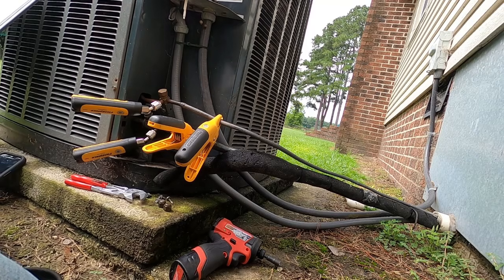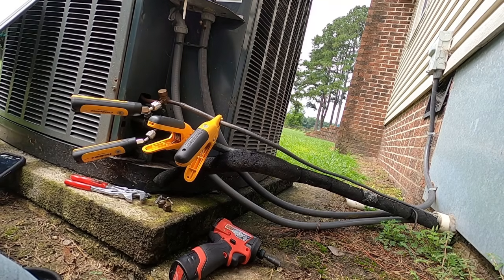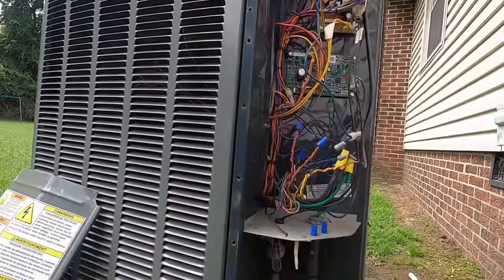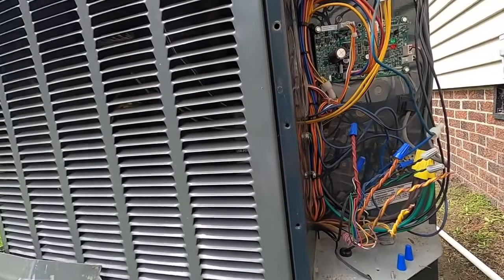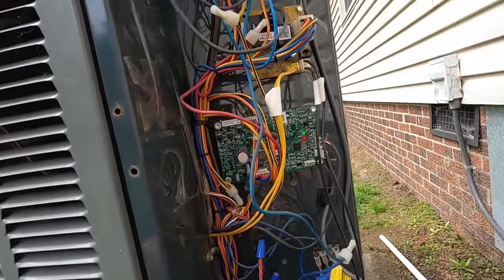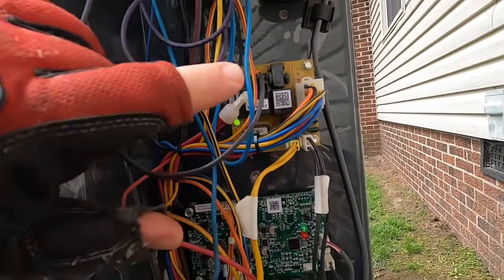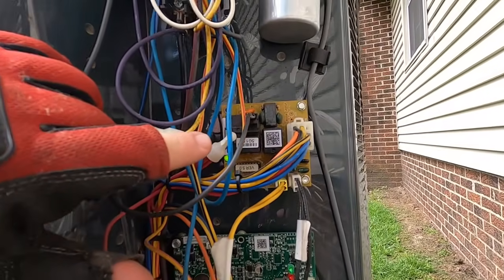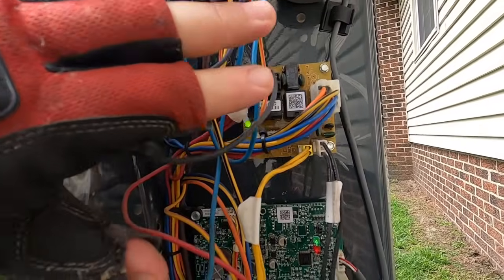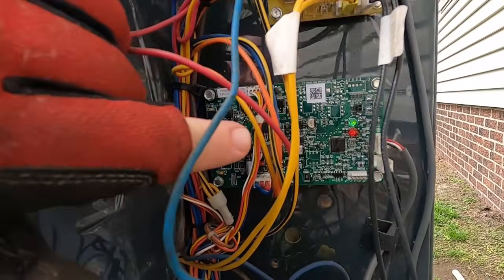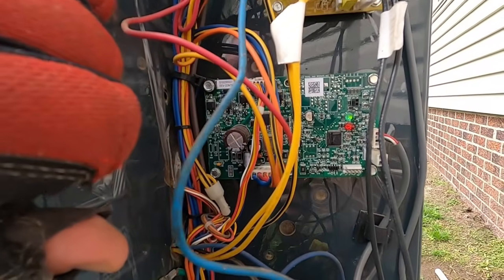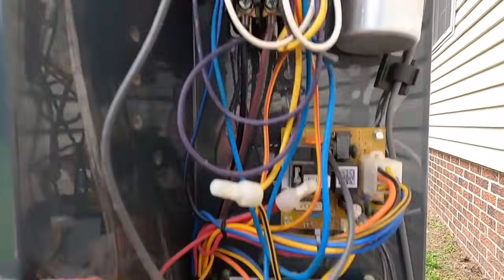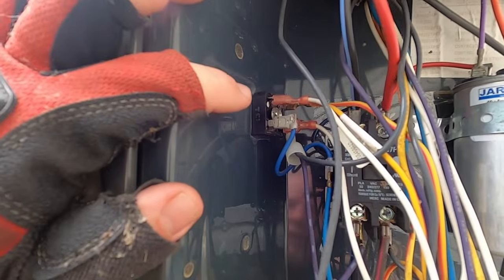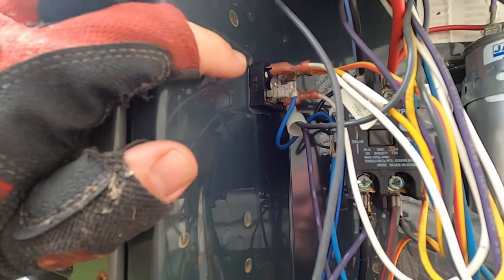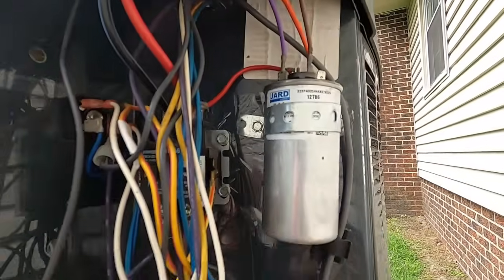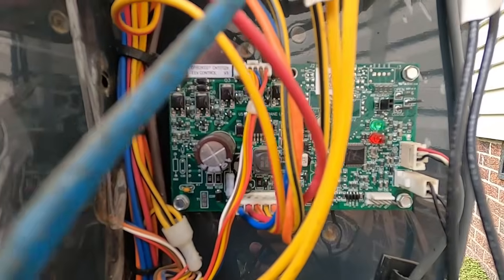Alright, we're back outside waiting for that thermostat to reboot and come out of delay. So I said, this 18i, you got a defrost board in it here, typical Trane defrost board. The newer ones, they don't use that board anymore. The newer ones look similar to this, as far as at least the way it looks anyway. Contactor, you got your DC, you got your rectifier there for your second stage. Obviously your capacitor, the EEV board for the outdoor unit.